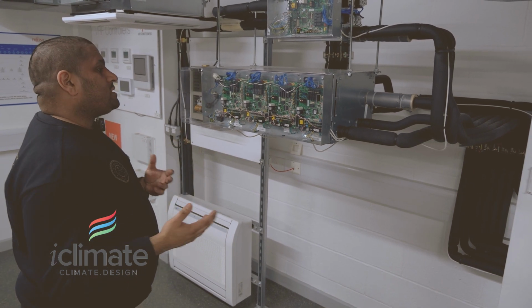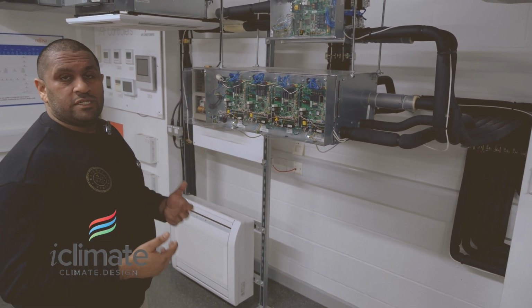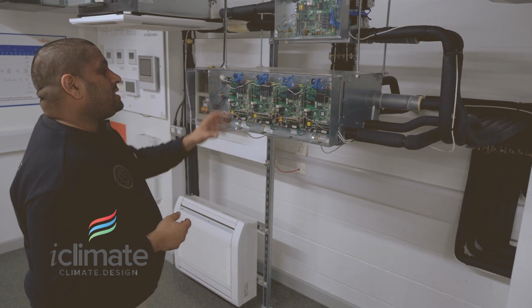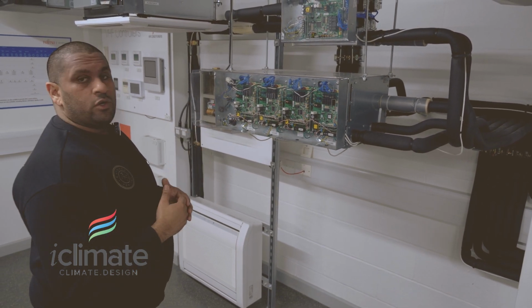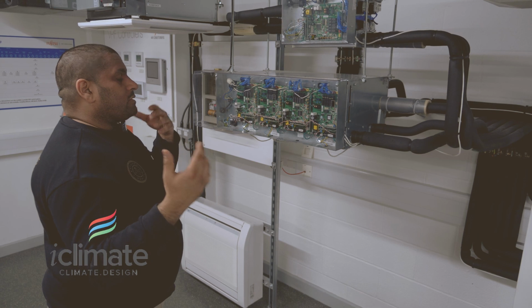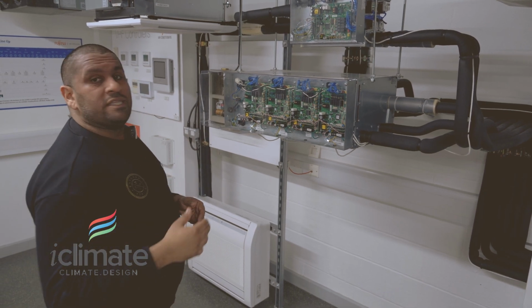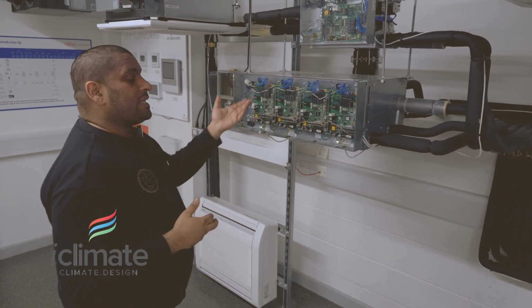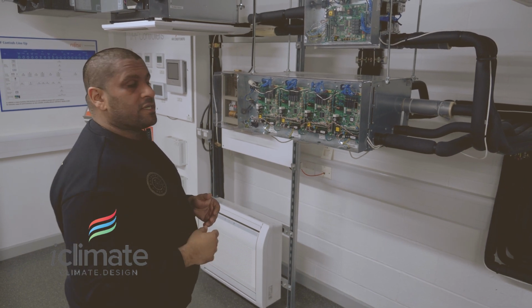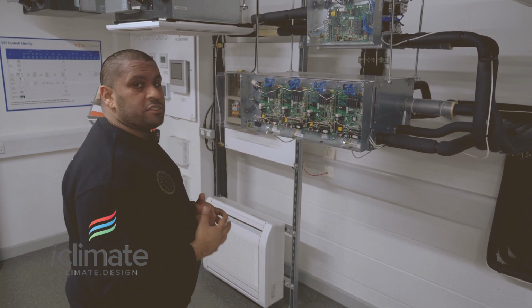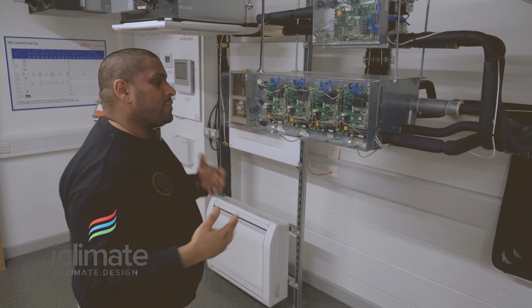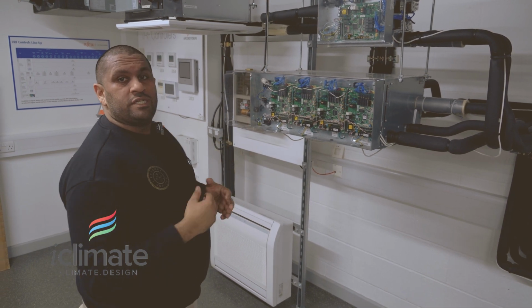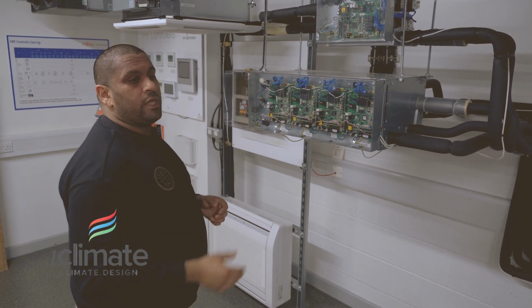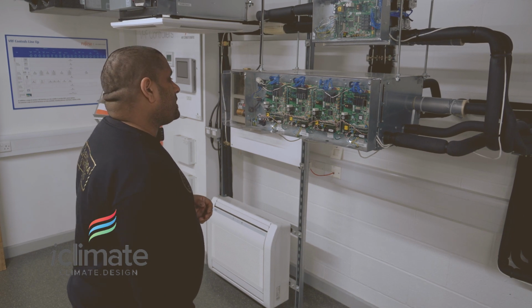Now, if the indoor units are on simultaneous modes of heating and cooling, the heat exchange can be done where the one unit that's doing a heating can then send its liquid refrigerant back to a unit that needs cooling instead of sending it back to the condenser. So this is where the term heat recovery comes from, because we're recovering the heat generated from the unit on heating, sending it over into cooling without putting any more load on the outside condensing unit.